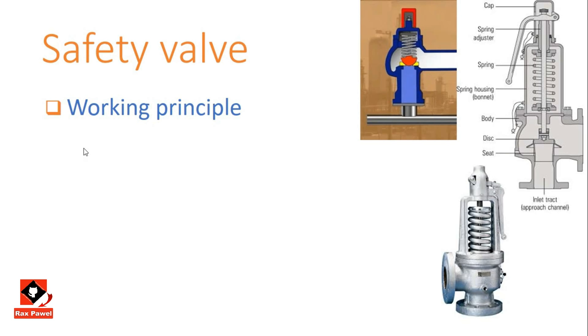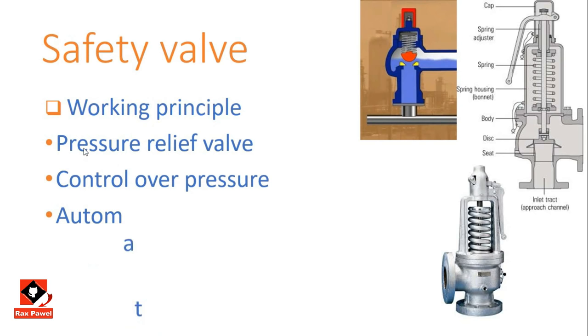Working principle of the safety valve: allowable pressure is balanced by a spring, and over-pressure conditions in the system are controlled by releasing the flowing fluid out of the system. Also known as a pressure relief valve, it works automatically to ensure safety when pressure increases. It can be used for both liquids and gases and is commonly seen in steam lines.